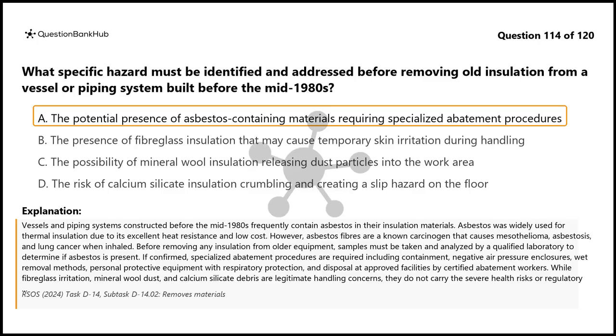Before removing any insulation from older equipment, samples must be taken and analyzed by a qualified laboratory to determine if asbestos is present. If confirmed, specialized abatement procedures are required, including containment, negative air pressure enclosures, wet removal methods, personal protective equipment with respiratory protection, and disposal at approved facilities by certified abatement workers. While fiberglass irritation, mineral wool dust, and calcium silicate debris are legitimate handling concerns, they do not carry the severe health risks or regulatory requirements associated with asbestos exposure.